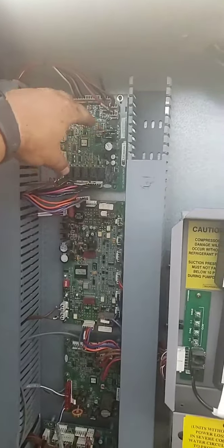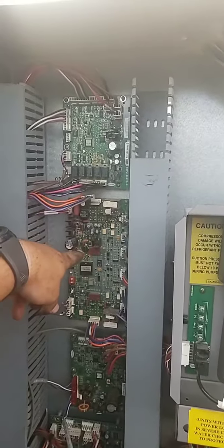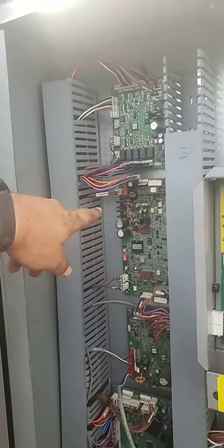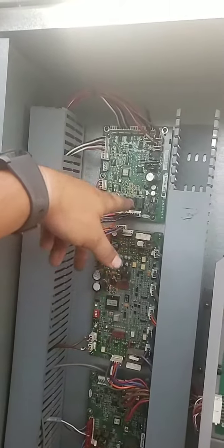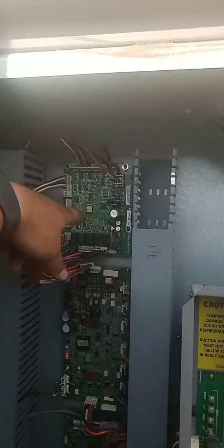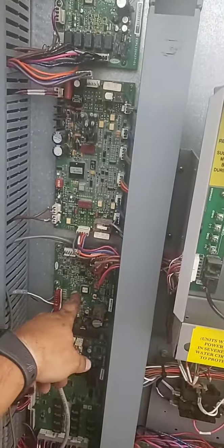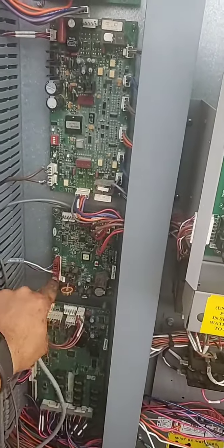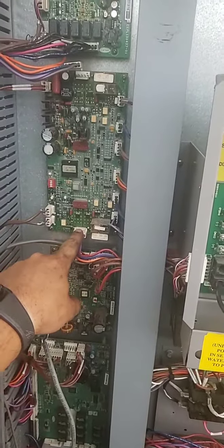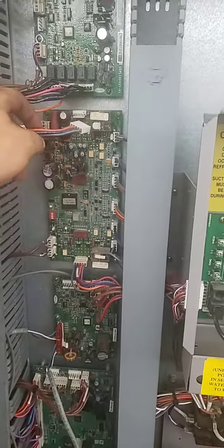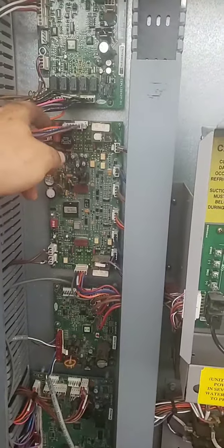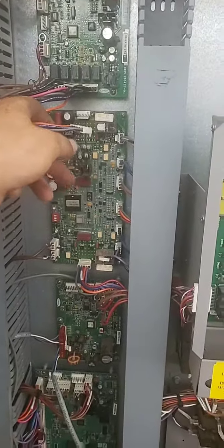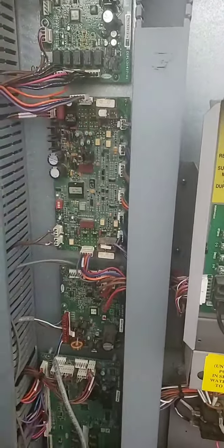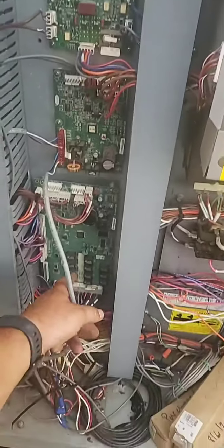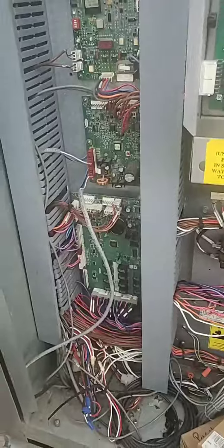this is your controllers here. This should be your CCP1. So this should be your main controller. This is also another relay board. Down here is your EXV board. These are your EXV terminals. These are your safeties. So this is circuit A safeties. Circuit B. Now I have circuit B safeties pulled because of the EXV being bad, and so I don't want that circuit to even try to run. And then you've got another relay board down here as well. So you can see some of your wiring diagrams there.